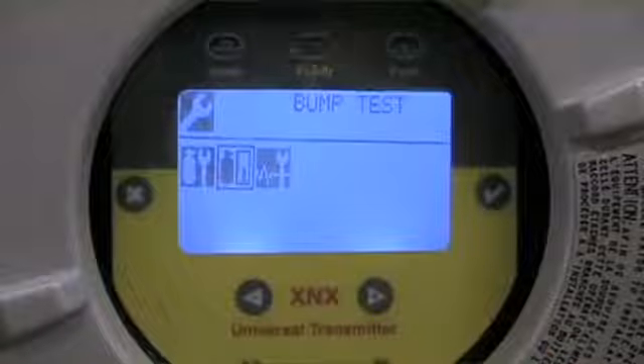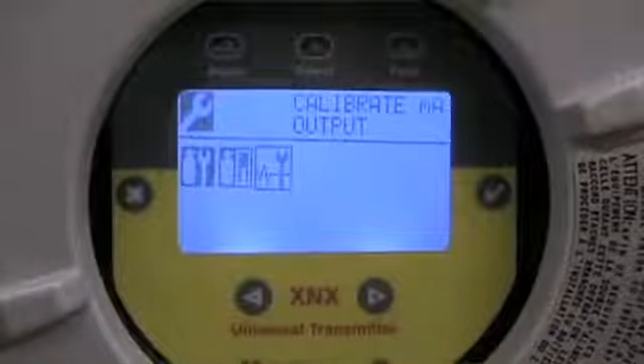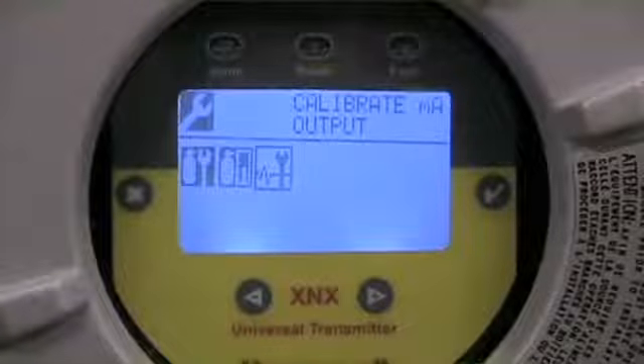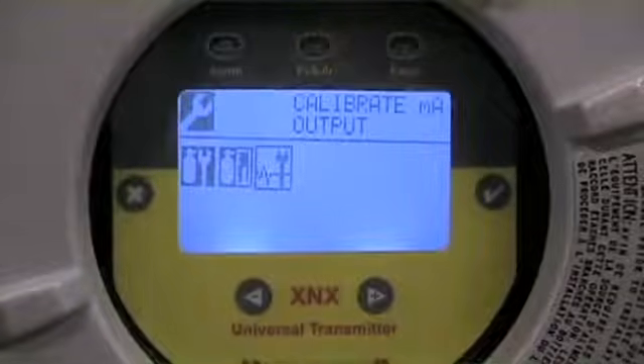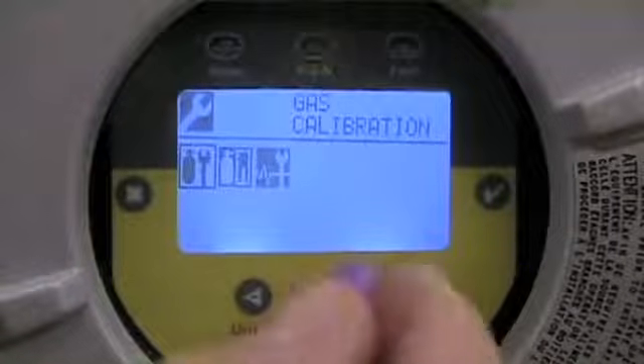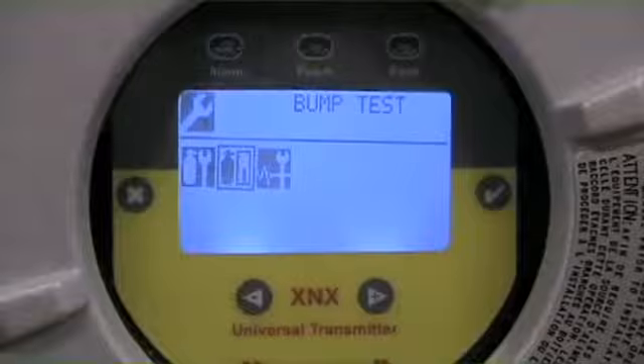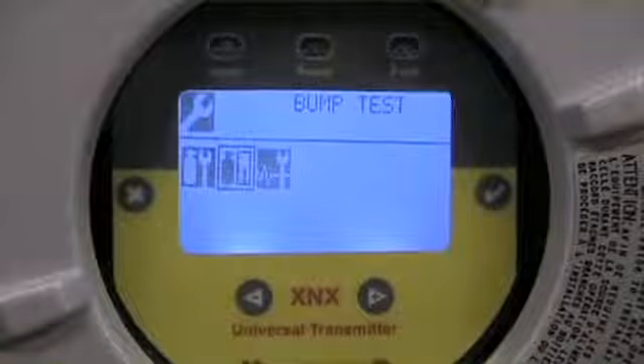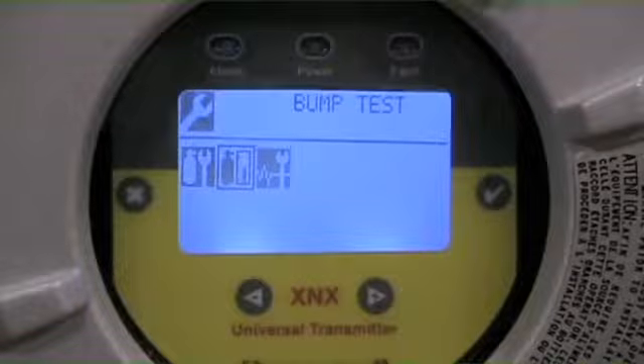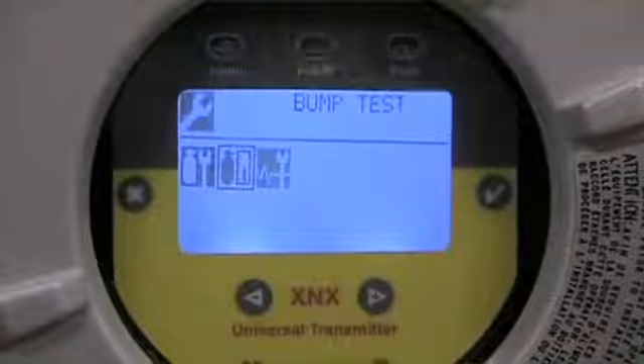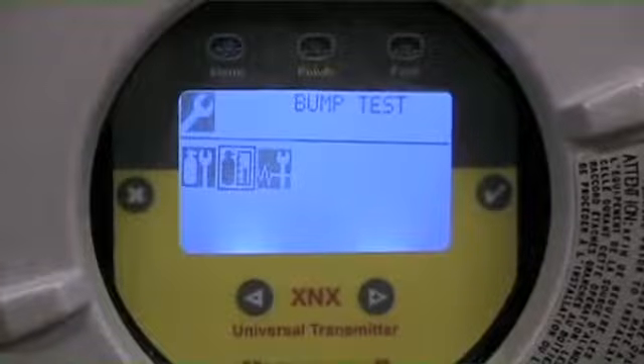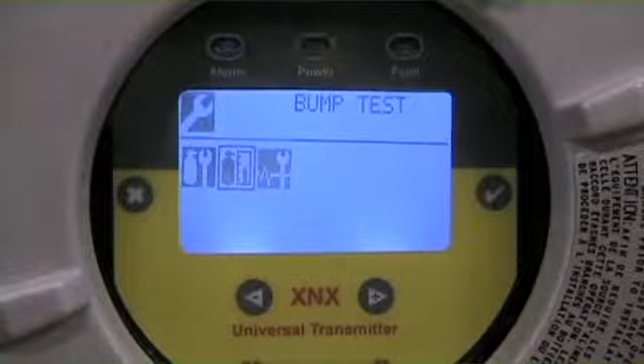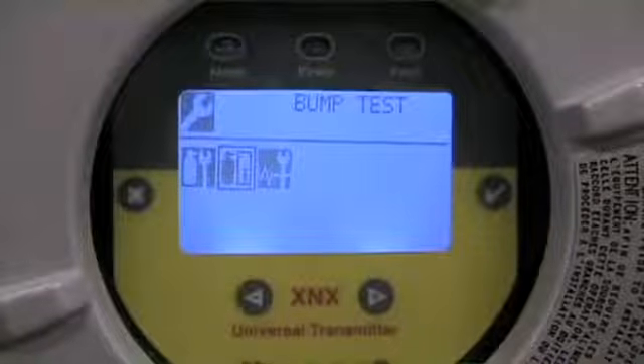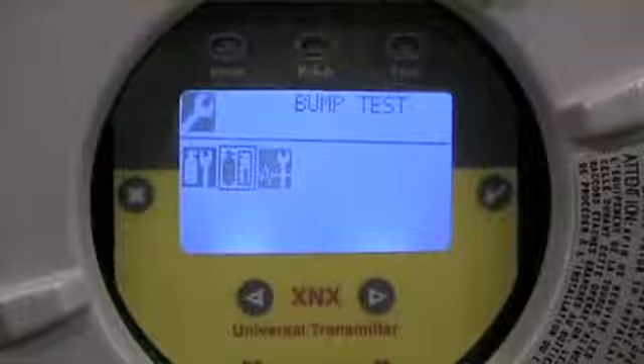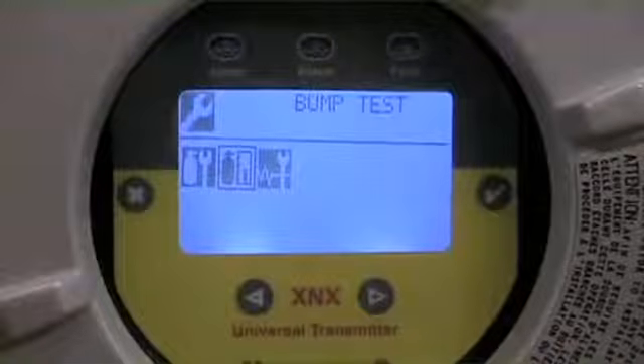Within the calibration menu, we've got actual gas calibrations. We've got things we describe as bump tests, and then we also do a calibration of the 4 to 20 milliamp output. We actually went through that menu in the loop verification video. For our purposes today, what we really want to start with is a bump test. Now in our world, a bump test is a way to check calibration performance. All the XNX sensors are pre-calibrated, and that calibration information is stored down in the sensor itself. So the intelligence is there with that technology. In some cases, people need to do bump checks where they just want to verify, not change a curve or output of the sensor, but verify that it's still in range. That, for us, is the bump test.